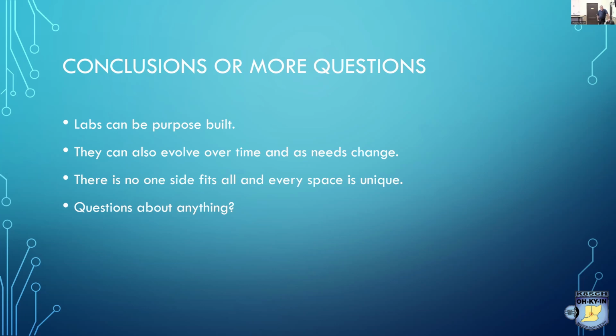However, the HP stuff, anything with crystals in it, they like to keep the crystals hot. One of my fellow YouTubers who has a bigger lab than I do, Shahriar from The Signal Path, actually measured it. He had a whole bunch of HP gear. He was burning a kilowatt continuous in standby just to keep the ovens warm. I did bring one of the time mark generators from Tech, one of the old ones. That's one of the biggest offenders. I think it's a 150 degrees C oven, and it burns that. If it's plugged in, it's cycling the oven just to keep it warm.